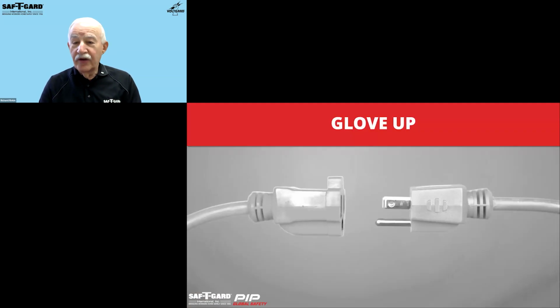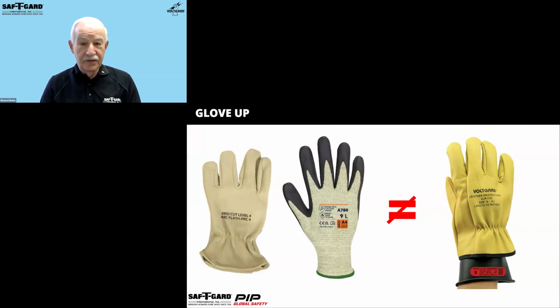Employees that work on electrically energized circuits and equipment use their hands, making them the most susceptible part of the body to electric shock. Rubber insulating gloves are the only protective gear designed for constant contact with and protection from energized conductors and equipment. All the other items are designed for protection from accidental, incidental, or brush contact. Now, there's a lot of products on the marketplace that claim to offer ARC ratings, but ARC-rated work gloves offer no shock protection. Let me repeat that. ARC-rated work gloves offer no shock protection, and most arc flash hazards have a shock hazard as well.